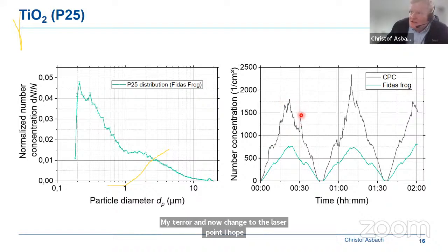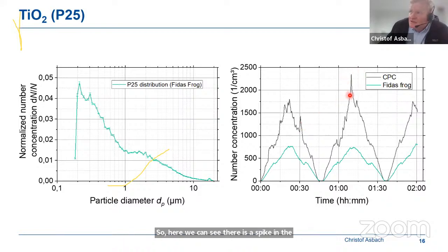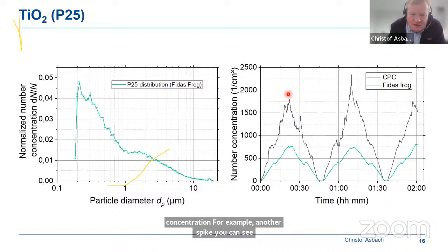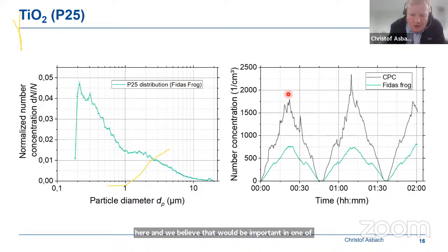So here we can see there's a spike in the concentration, for example, another spike we can see here. And we believe, and that will be important in one of the next slides, we believe that these spikes come from bursts of very small particles into the measurement system. We don't really know where they came from, but since they're very small, the CPC can detect them and the FIDAS frog cannot.